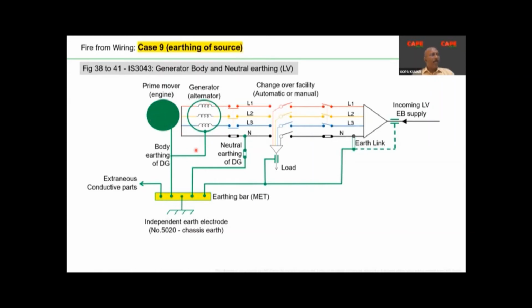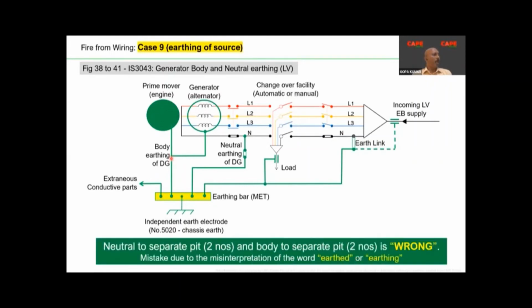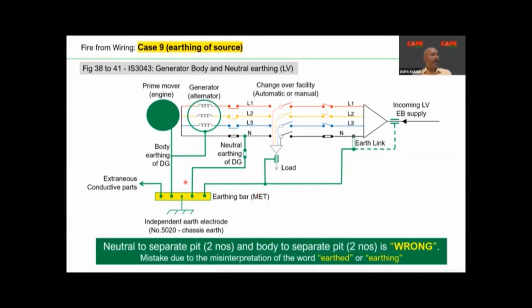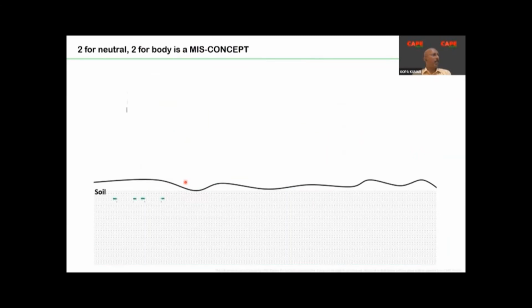Actually, this picture, what I have shown, is from the IS standard. This picture has existed in the standard for 40 years, but even today, nobody follows this. Transformer neutral is connected to 2 separate earth pits. Body is connected to 2 separate earth pits. DG neutral separate, DG body separate, and everything is separate, connected to different earth pits or earth electrodes in soil. This is absolutely wrong. You must make a proper earthing system by interconnecting exposed and extraneous conductive parts.